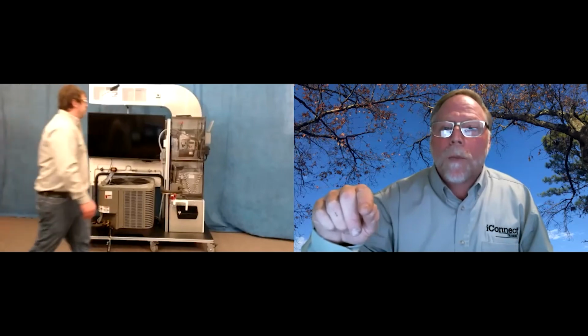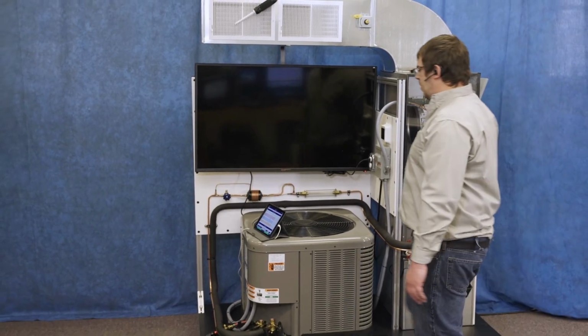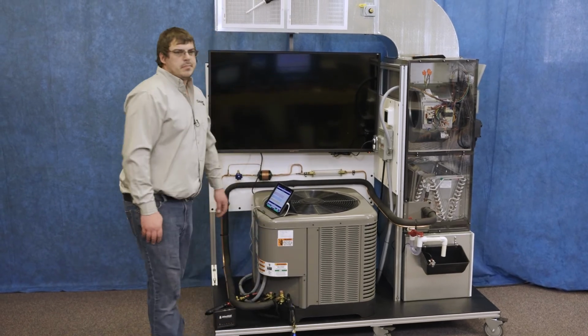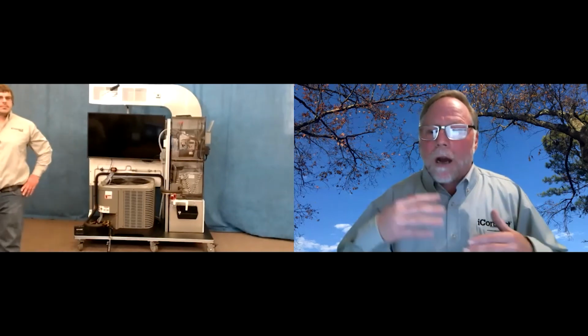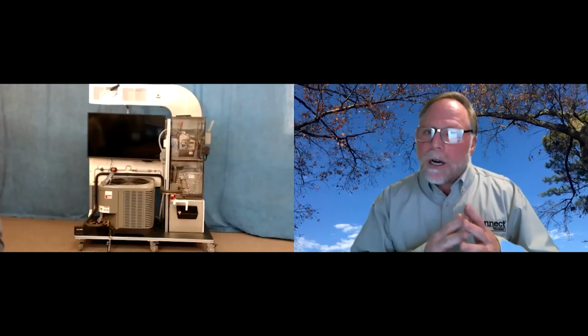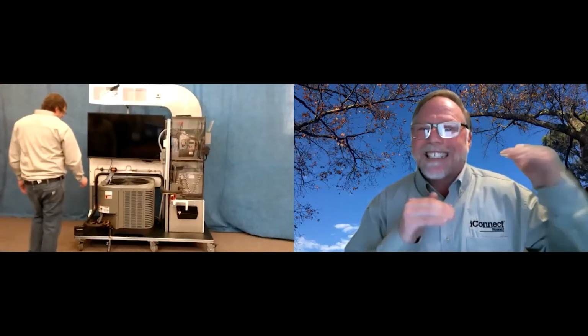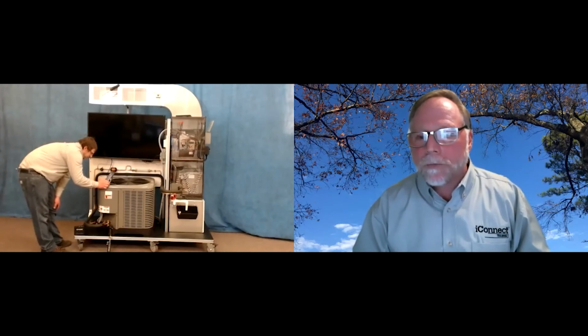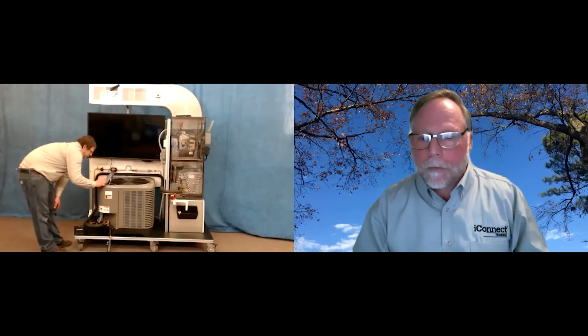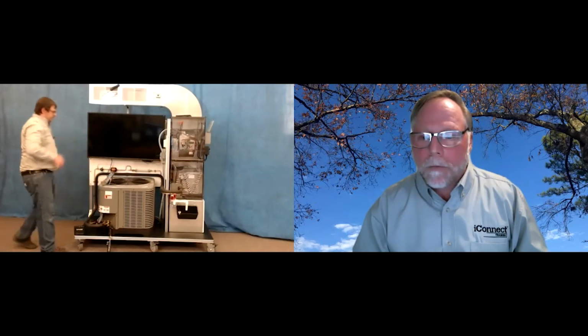Now go ahead and turn the indoor fan all the way off. This is going to simulate a loss of indoor fan. The one thing you'll find out on these trainers too is that as we're operating, you've got to give it a minute to adjust, because the indoor and outdoor coil are in the same load conditions. Now we can see how the relative humidity and the wet bulb are changing on it. There goes our dry bulb changing on it. So we've got an immediate change due to no airflow.